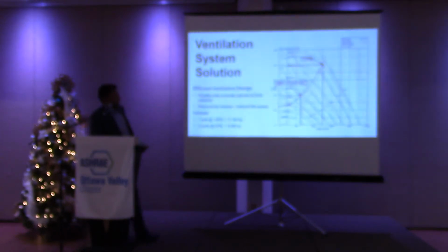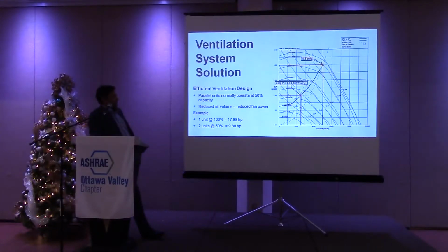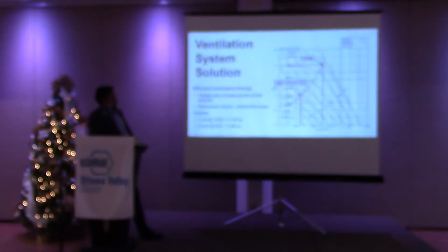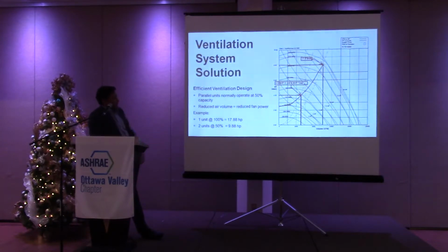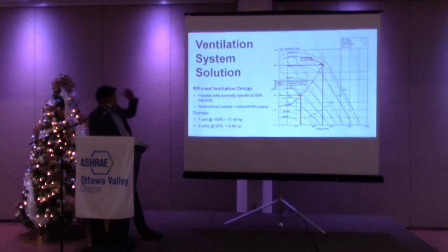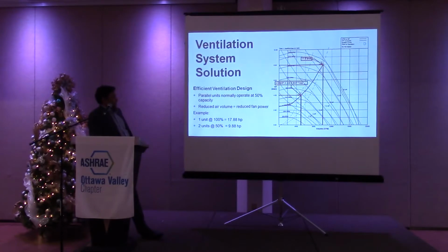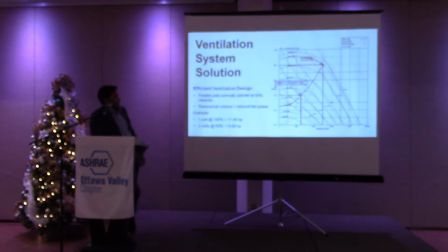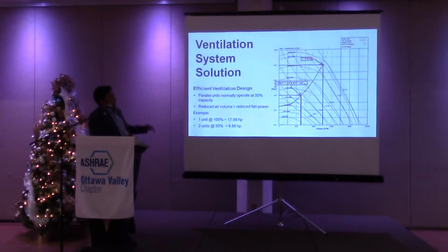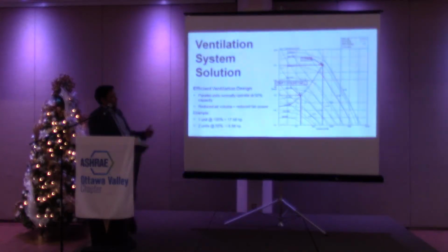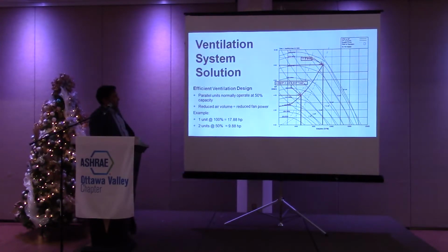So just going back to reduced fan energy, for the students in the room, your fan affinity laws. But basically, if you have 2 units operating at 50% capacity, in this example, we say 1 unit at 100%, you use 17.8 brake horsepower. 2 units at 50%, you use 9.8. So you can look at the fan curves there, and you can see significant energy savings that we get all the time unless you're doing maintenance. So the reality is probably 99% of the time you're getting benefit of those savings.